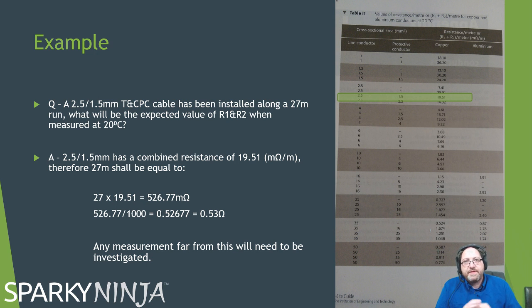Alright, this is a picture from a table in your On-Site Guide. This table is also in Guidance Note 3, and it's also, I think, in the PAT testing code of practice. If you're going to do a test for R1 plus R2 on a cable, you need to know its length. Hopefully the drawings will help you with that. You need to know its size. You can then decide whether to accept the number.